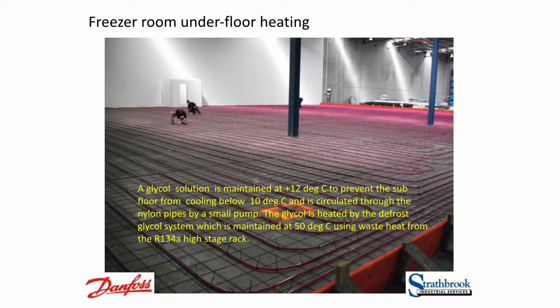So the floor heating there, you can see that's a nylon pipe. There's about 2 kilometres of tube there. We take heat out of the discharge, we heat that glycol up to 50 degrees to do the defrosting of the evaporators, and then we heat 12 degree glycol off the 50 degree glycol and pump it through the floor to stop the subfloor from freezing and destroying the floor.